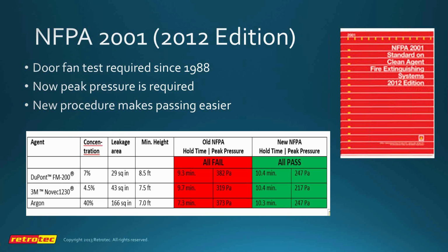That's what we've modeled our new enclosure integrity software on, and it would mean, say, for the inert agent enclosure, that we might be saving $20,000 in air sealing or something. Air sealing can be expensive. I've known of many people that have spent a small fortune trying to get these rooms tight enough, and so the advantage of using the 2012 version is that we've made life a bit easier for you.